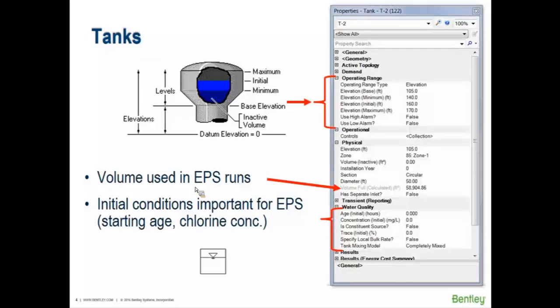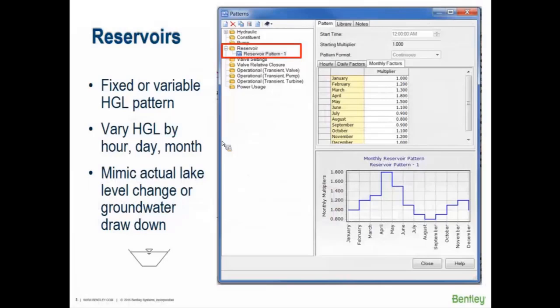For the first few days we're only running a steady state model — not extended period simulation nor water quality — so I'm just introducing these as properties held in a tank. For reservoirs, you can assign a pattern that adjusts the head by hour, by day, or by month — perhaps for a clearwell, groundwater source, or lake reservoir to simulate changes in elevation.